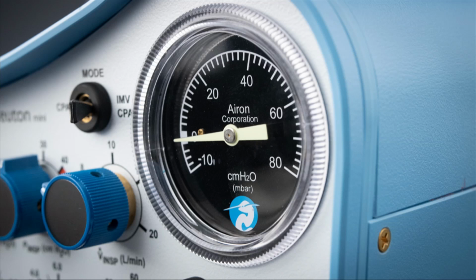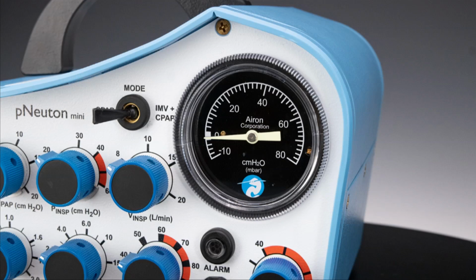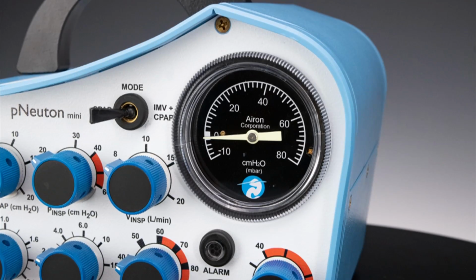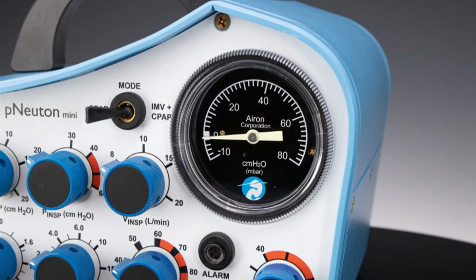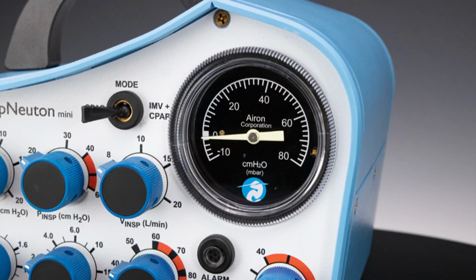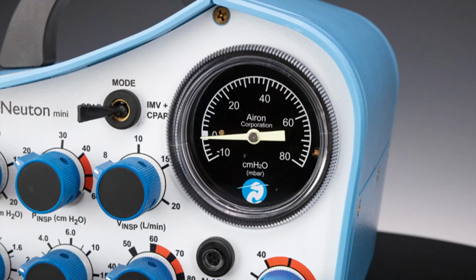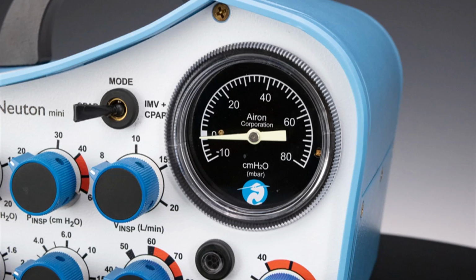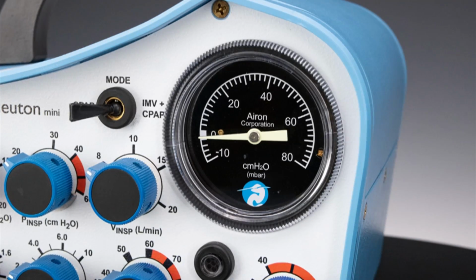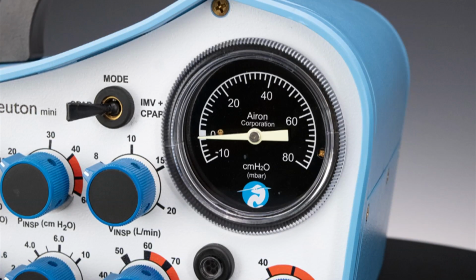The pNeuton mini manometer, or pressure gauge, represents proximal pressure in the patient circuit measured at the patient Y. The pressure gauge provides a visual indicator of patient pressure for the CPAP PEEP and the delivered airway pressure for each breath. The alarm system uses the proximal patient pressure signal. It is in line with the pressure gauge, so the measured pressure shown on the pressure gauge is the same as the alarm system pressure trigger.